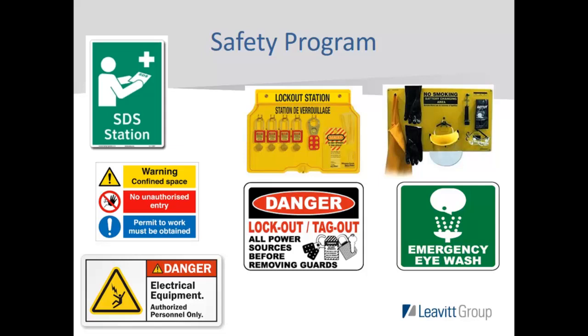Equipment that requires a lockout tagout procedure should be identified with graphics on that particular machine or equipment. The equipment-specific lockout tagout procedure must be readily available to the employees authorized to perform the procedure. Placing this documentation and locks at a single lockout tagout station is a great way to ensure that you have, number one, a lockout tagout program, and that it is actually compliant with OSHA regulations.